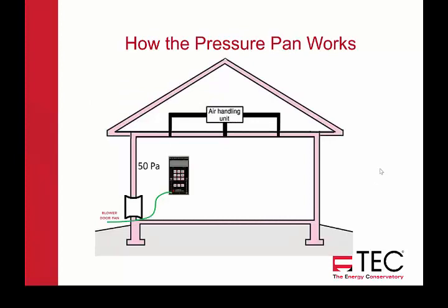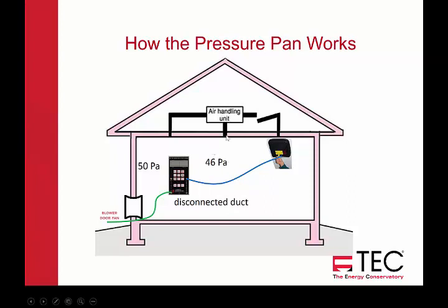How the pressure pan works: bring the house to 50 pascals and put the pressure pan over the opening. If you're getting zero pascals with that duct, you know that duct run is very tight — low numbers mean tight ducts. If you're getting a really high number — for example, your house is at 50 and you're reading 46 pascals — it's likely disconnected and reading the pressure in the attic rather than the pressure in the duct system. Really high numbers are an indication of a disconnect or a partial disconnect.